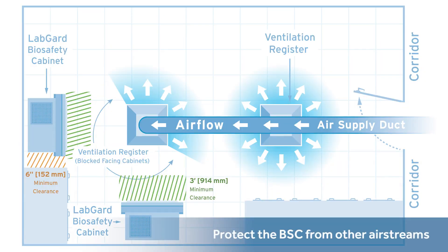Industry guidelines recommend that laboratories deliberately distance their biosafety cabinets from places where people walking alongside them or other airstreams might upset their own airflow dynamics. For the same reason, they advise that you limit other staff's movements within the vicinity when you are using a cabinet.